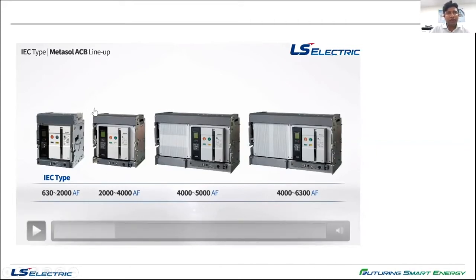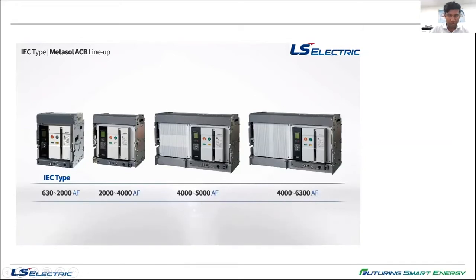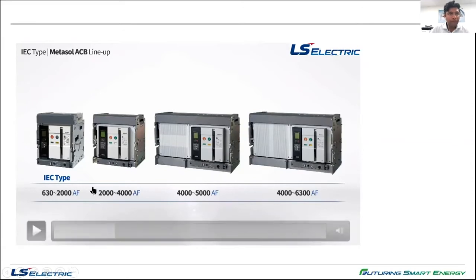The second frame size, we recommend using from 2000 amps up to 3200 amps. And the third frame size for 4000 to 5000, and the final one from 4000 up to 6300 ampere frame size. Now, if you see, these are the 4 different frame sizes.